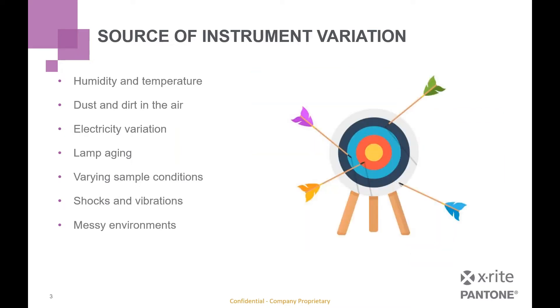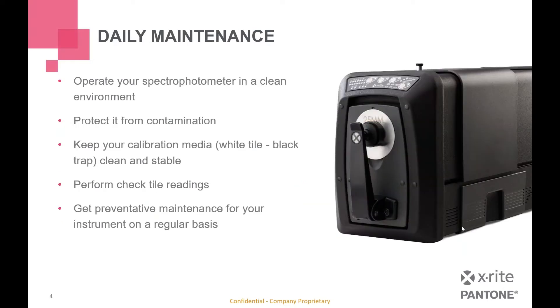What this leads to is a scattering of measurements. As contamination gets in, the calibration may come off with those instruments, leading to your measurements circling the mean or the true value of that color measurement. The first line of defense is daily maintenance of that device — operating in a clean environment, making sure laboratory equipment is kept in the best conditions possible, protecting it from contaminants in the air, particularly with calibration media, making sure that media remains clean and stable. Some instruments also have check tiles that can be performed. In addition to daily best practices, annual certifications and preventative maintenance are an important tool to make sure the device is clean and certified back to factory settings.